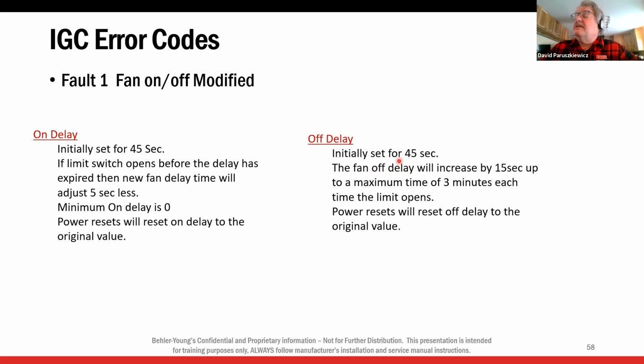If the blower shuts off and the limit trips while the blower's off, then it's going to add 15 seconds to the blower off time. So if at 45 seconds the blower shuts off, and then a couple seconds later the limit trips, the next time the blower will shut off in 60 seconds. And then it'll go to 75 seconds, and then 90 seconds, all the way up to 3 minutes. So if you've got that light flashing one time, it just means that this has been altered. This is the only way to adjust the blower time. It's going to adjust itself in the limit trip. Okay.